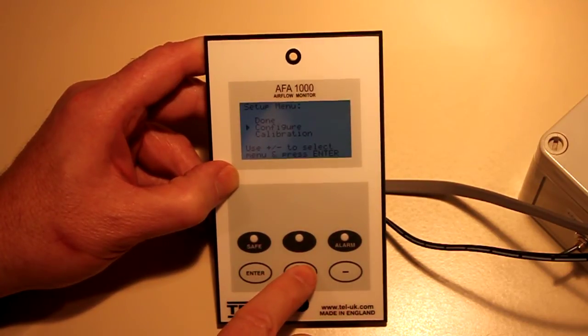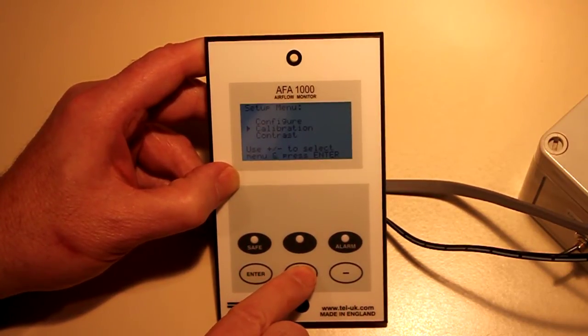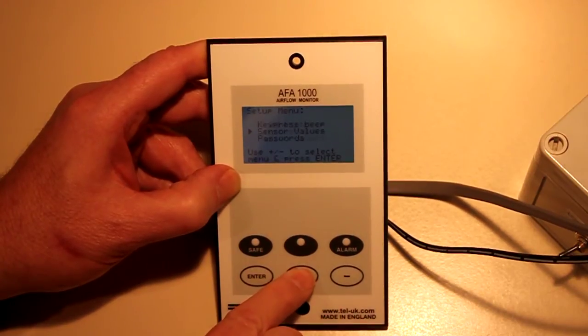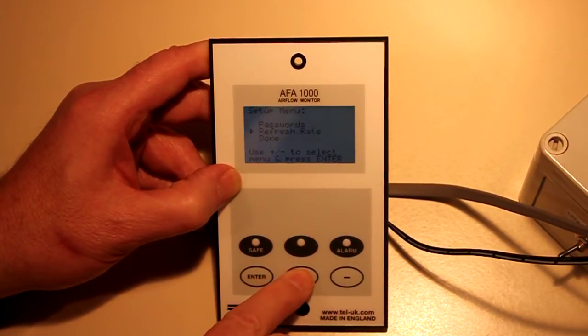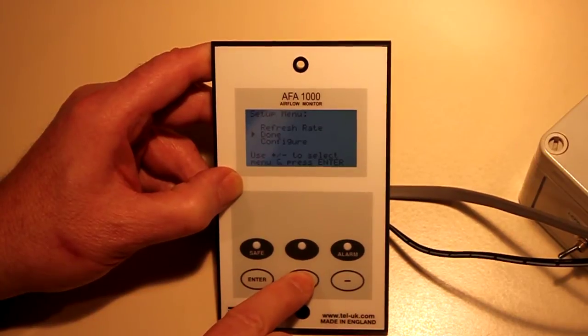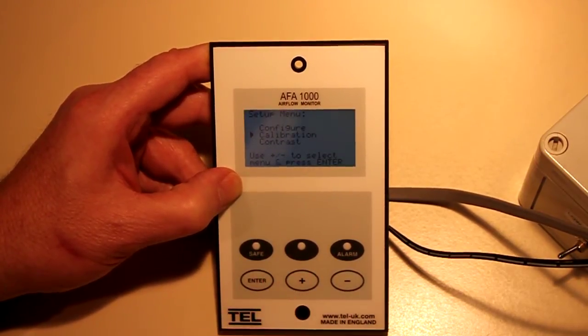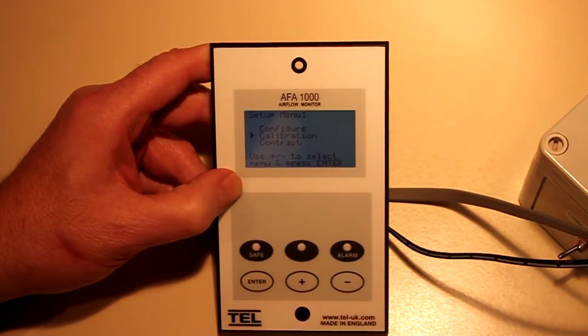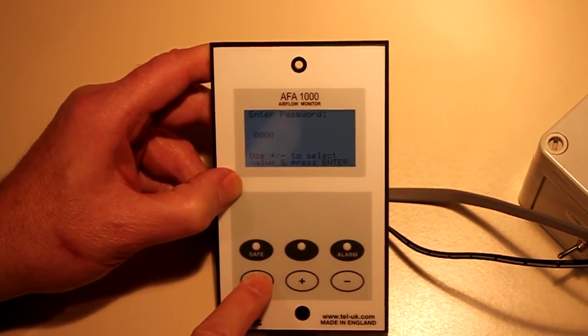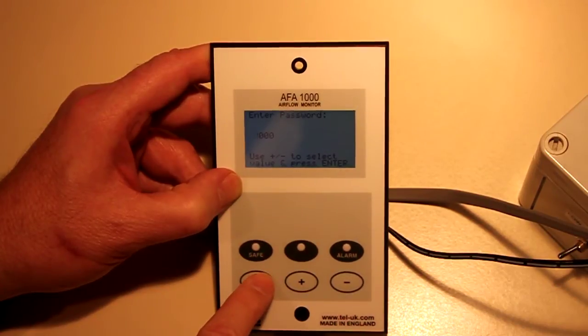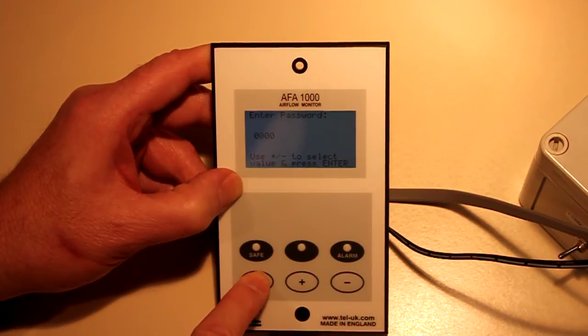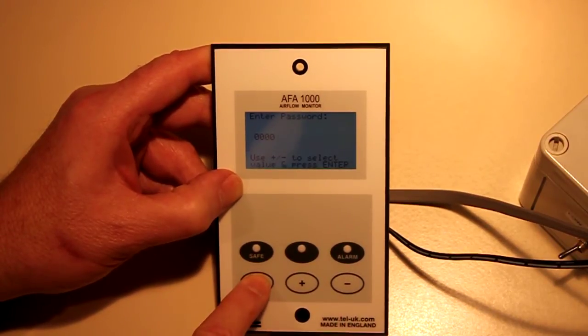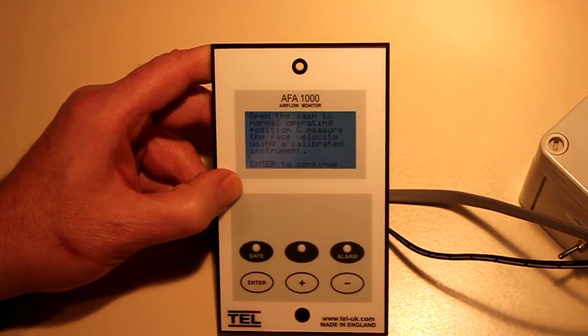The Setup menu has several options: Configure, Calibration, Contrast, Passwords, and Done. Configure is used to set monitor hardware and installation parameters. One step past the Configure menu is the Calibration Configure menu, which is used to set calibration and operations parameters. To calibrate the sensor, select Calibration. This brings up the password screen. The factory default password is 0000, which is what appears on the screen. Press the Enter button 4 times to move the underscore through each digit and begin the calibration process. Once there, follow the instructions on the screen.